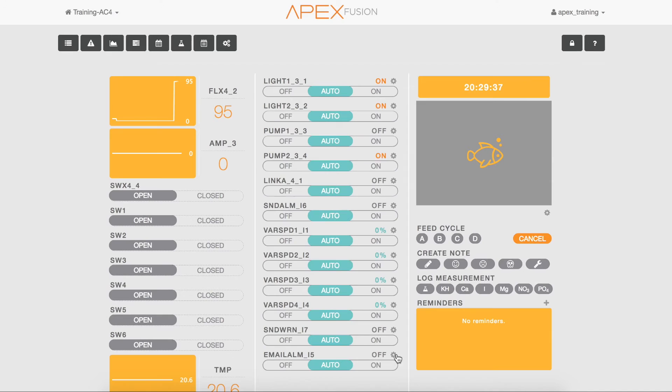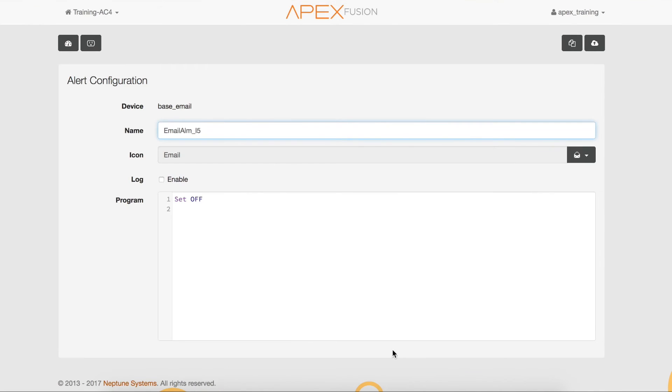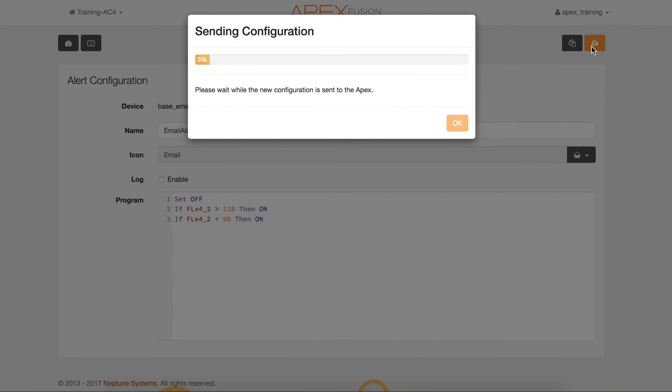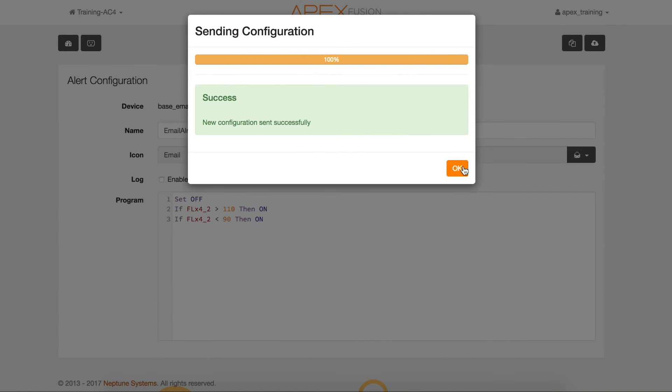To set up an email alarm for your flow sensors, click on the gear icon next to the email outlet on the dashboard. When programming outlets in Fusion, there is an advanced editor that will help you autofill your programming — just type in the first letter of a command and it will show all valid options. The programming shown here says: if the flow sensor on port 2 of the FMM at address 4 detects flow greater than 118, or less than 90 gallons per hour, then turn on the email alarm. Once programmed, select Save and then OK.